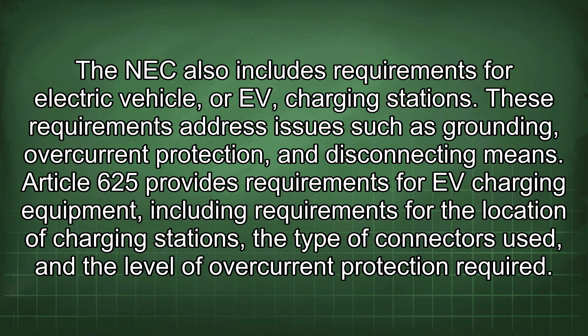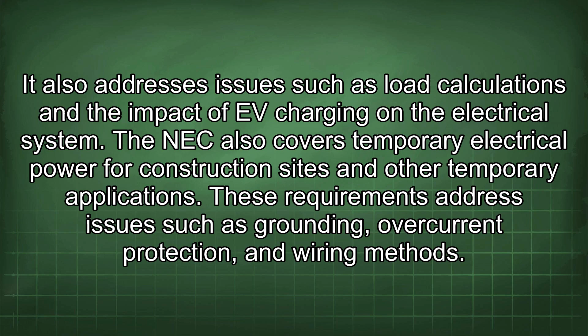The NEC also covers temporary electrical power for construction sites and other temporary applications. These requirements address issues such as grounding, overcurrent protection, and wiring methods. Article 590 provides requirements for temporary electrical power, including requirements for ground fault protection for personnel, or GFCI protection, and the use of weatherproof enclosures. It also addresses issues such as the inspection and maintenance of temporary electrical systems.